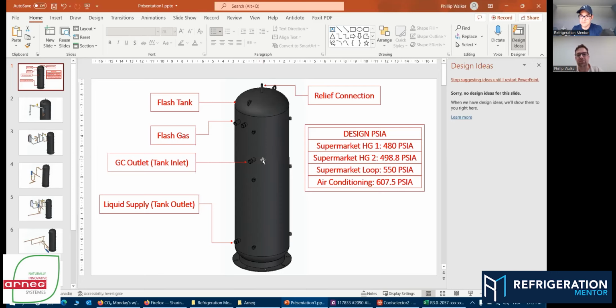We're always going to use 3 or 4 optic eyes, which you can see here. But where we start differentiating in the type of drum from standard refrigeration is really take a look at these inlets and outlets. Flash gas, basically we're going to put it on the top. Here's our GC outlet or the tank inlet, and here's our liquid.